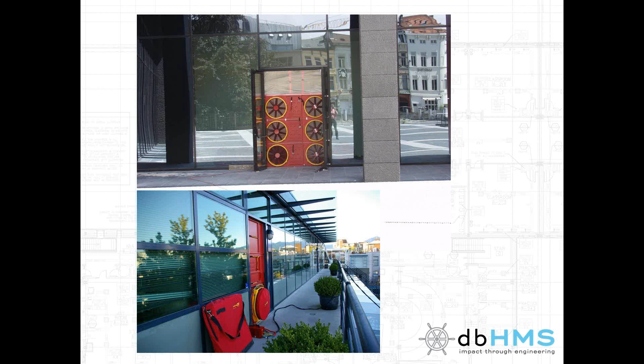So here you see a rig for a whole building pressure test. Those fans have different inserts, rings that go in and change the amount of air the fan will move, and the RPM of the fan is measured by the computer, which has the fan curve in it, so we know exactly how much air is going into the building. We know the differential pressure between the inside and the outside, so we can get a reading. Next slide.